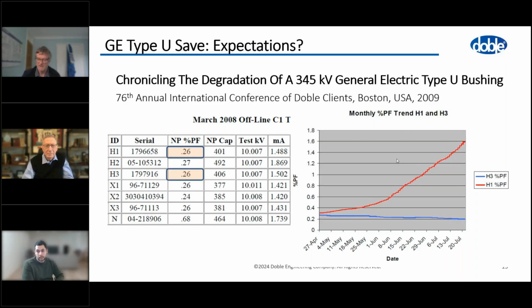And you can see from the table on the left, we're looking at H1, H2, H3, where H2 has already been swapped out because it was deteriorating. H1 and H3, we started monitoring those on the 27th of April 2008, so it's a while back. And you can see how the power factor on H1 rises.